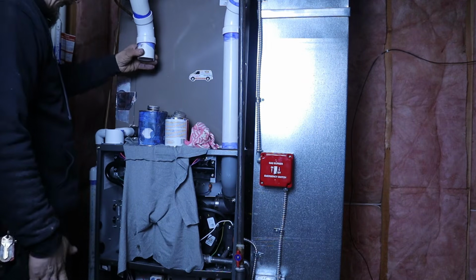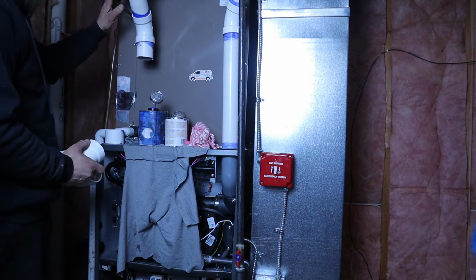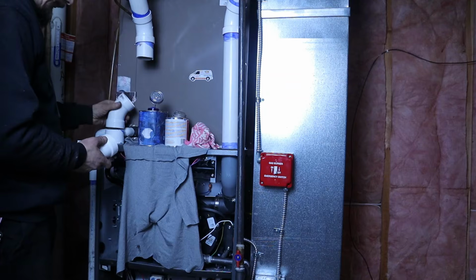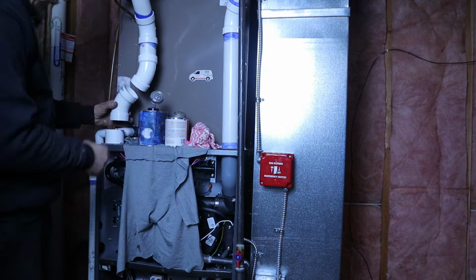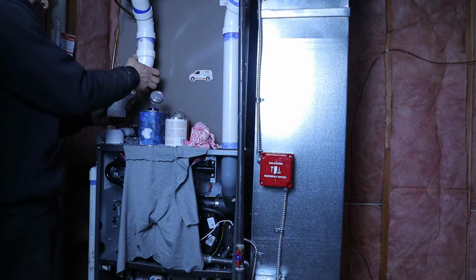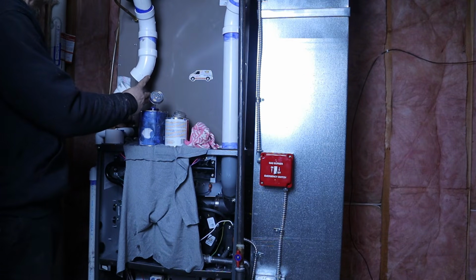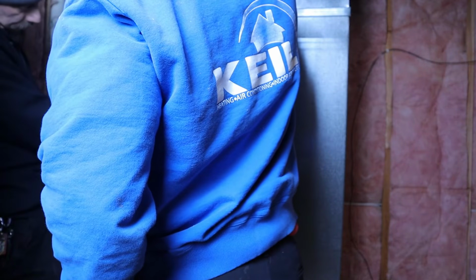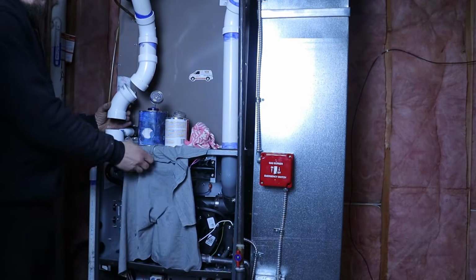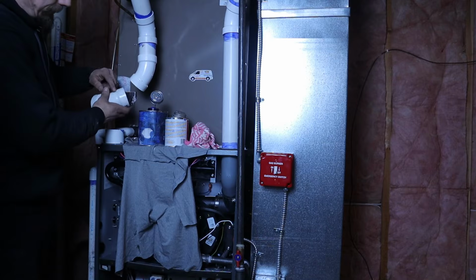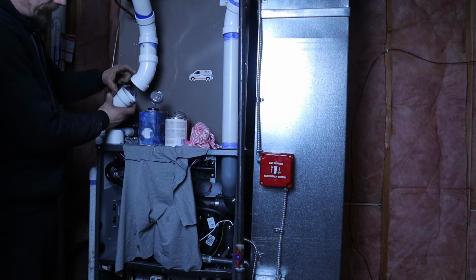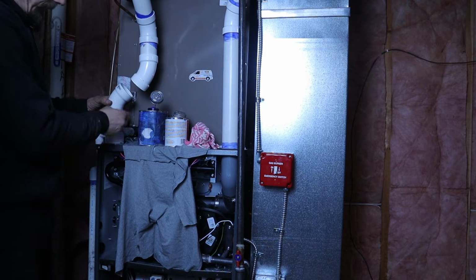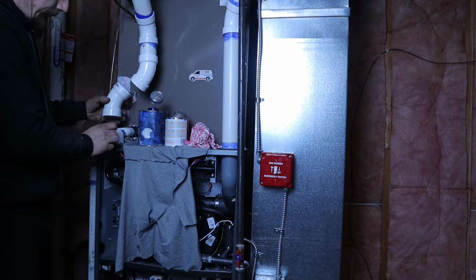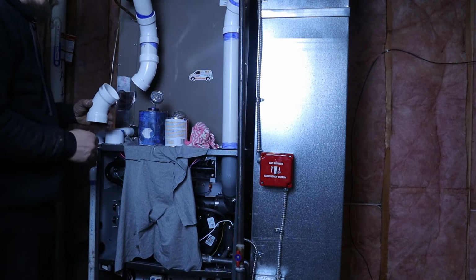Now we got to do our fresh air. I would have liked to come straight down with it to make it look all nice and neat, but we got copper in the way up here, so we have to offset it a little. So I'm just going to kind of size it up. So right there, I want to get a measurement. Make it 3.5. So what we're doing here is we're measuring from the bell to the other bell in here. So it's not just a distance here, it's actually inside the fittings all the way. So we got 3 inches there. I'm going to have him cut that. Then we'll take another measurement here into a coupling that goes into our fresh air intake. 3.5. Yep.